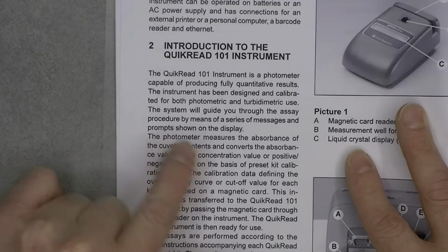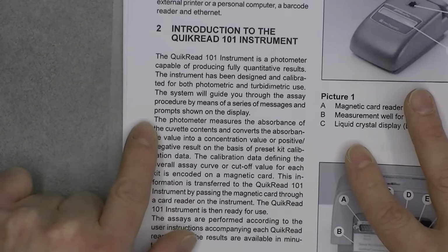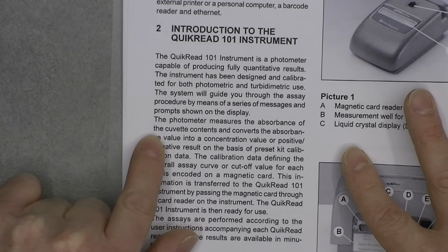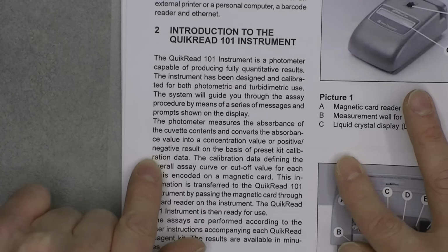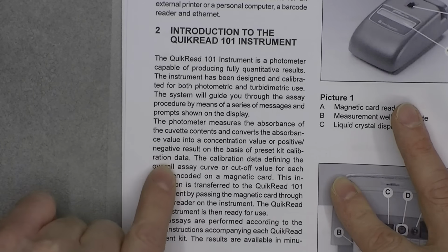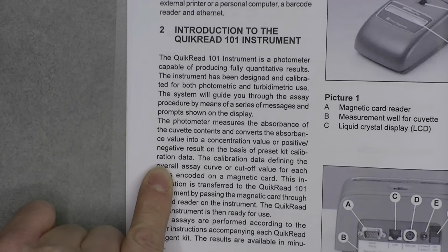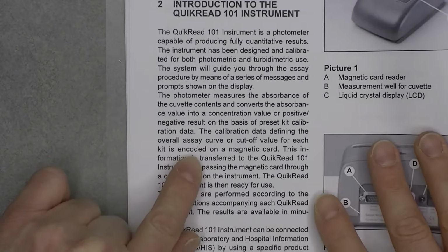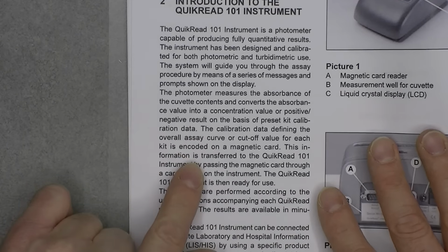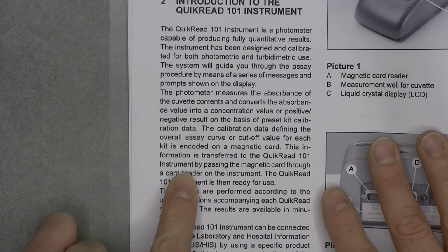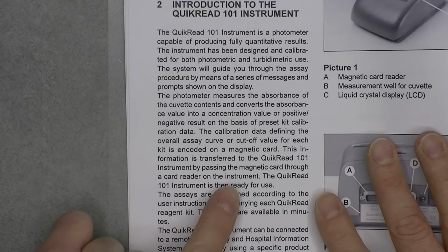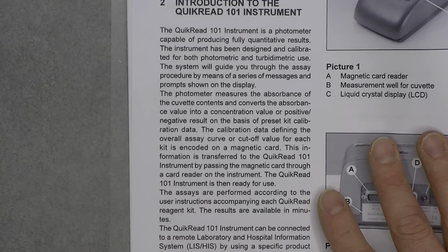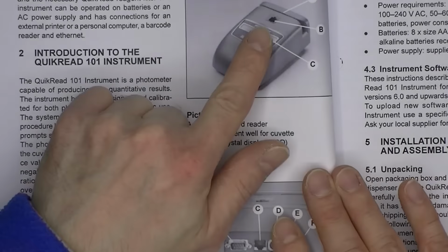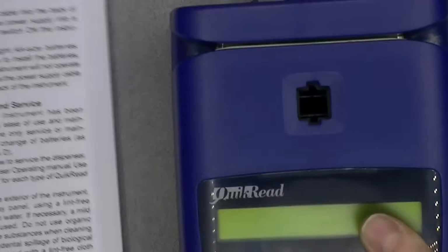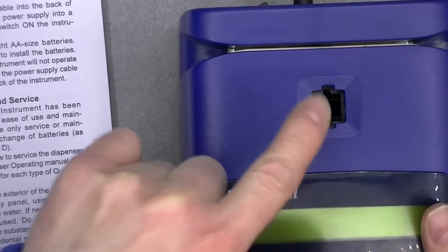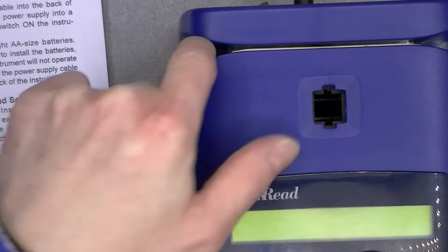So there is a display telling you what to do. The photometer measures the absorbance of a cuvette contents and converts the absorbance value into a concentration value or positive negative result on the basis of preset kit calibration data. The calibration data defining the overall assay curve or cutoff value for each kit is encoded on a magnetic card. This information is transferred to the QuikRead by passing the magnetic card through a card reader. Okay, so that is why we have a receptacle for, let's show directly on this, the test tube or cuvette or whatever, test container, and your magnetic card reader.